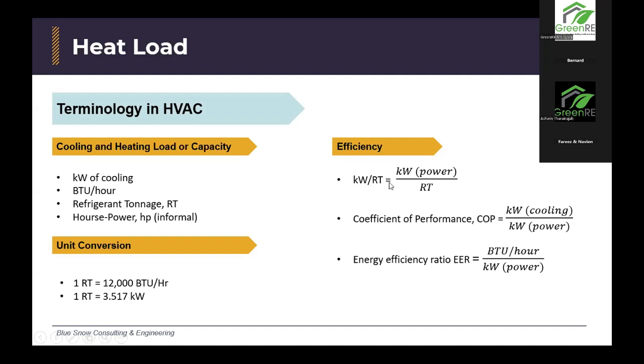The formula throughout all these three is always the same, where we compare the electrical use with the heat load or heat capacity required or being used. The next one is the coefficient of performance, also known as the COP, which is widely used in most equipment. The kilowatt on top is the kilowatt for cooling, divided by the kilowatt for power or electricity consumption. The next one is the energy efficiency ratio, EER. This one uses BTU per hour divided by kilowatt of electrical power.